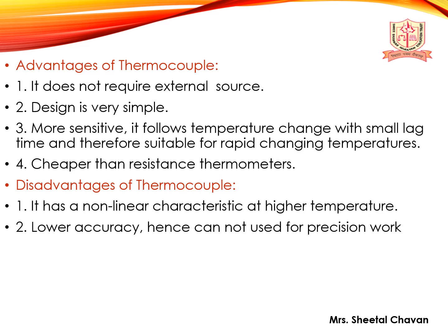Advantages of thermocouple. It does not require an external source. Second, the design is very simple. Then, it is more sensitive. It follows temperature change with a small lag time and is therefore suitable for rapidly changing temperature. Then the fourth one is that it is cheaper than the resistance thermometer.